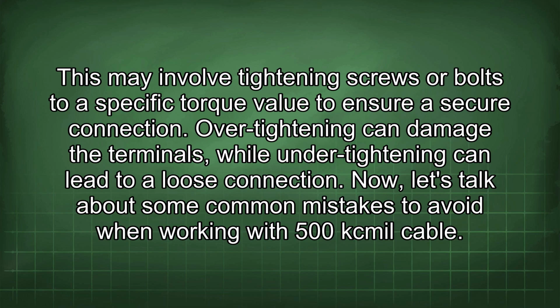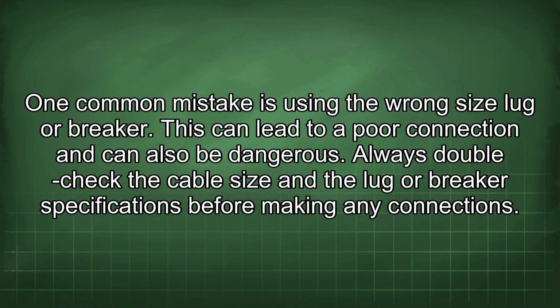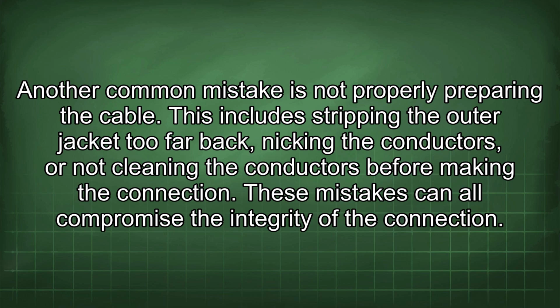Now let's talk about some common mistakes to avoid when working with 500 kcmil cable. One common mistake is using the wrong size lug or breaker. This can lead to a poor connection and can also be dangerous. Always double-check the cable size and the lug or breaker specifications before making any connections. Another common mistake is not properly preparing the cable. This includes stripping the outer jacket too far back, nicking the conductors, or not cleaning the conductors before making the connection. These mistakes can all compromise the integrity of the connection.